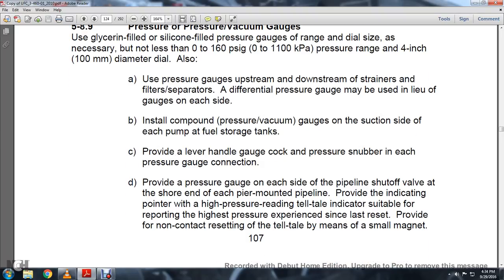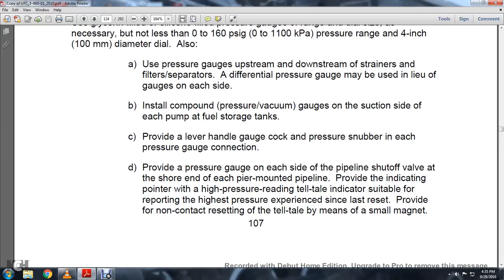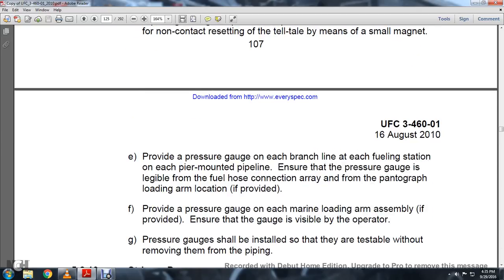Provide a pressure gauge on each side of the pipeline shutoff valve, mounted on the short end of the pipeline. Provide a telltale indicator suitable for indicating the high pressure reading, showing the high pressure since the last reset. Provide non-contact resetting of the telltale with a small magnet. Provide a pressure gauge on each branch line of the fueling system.